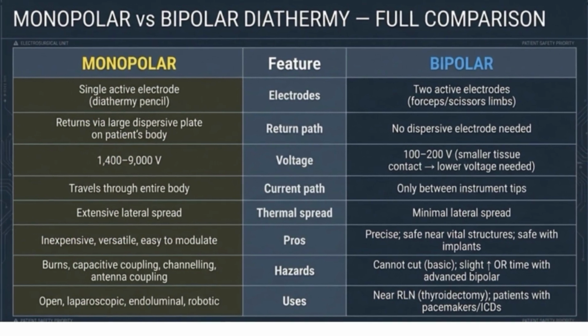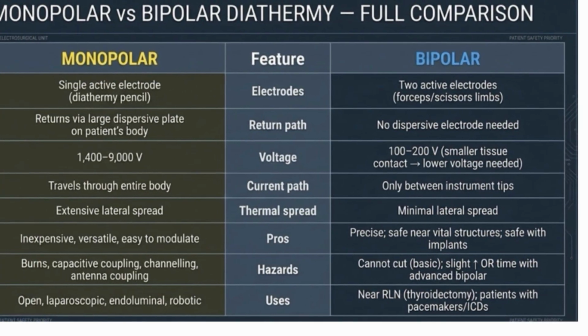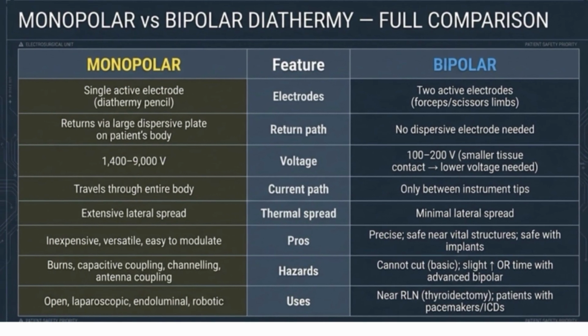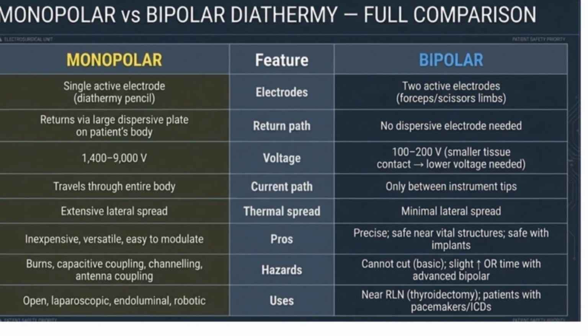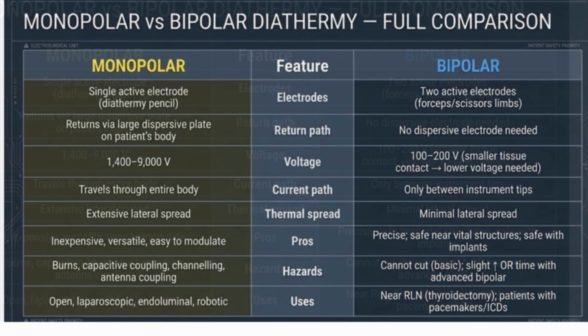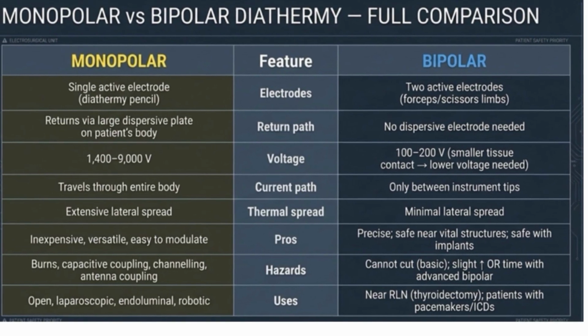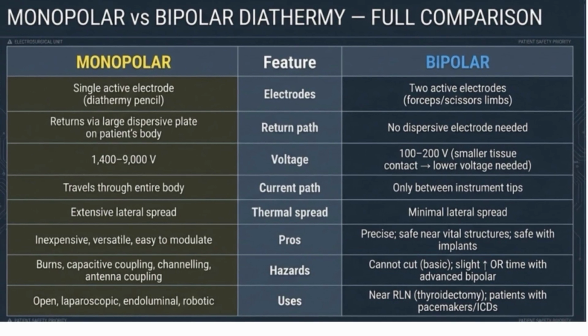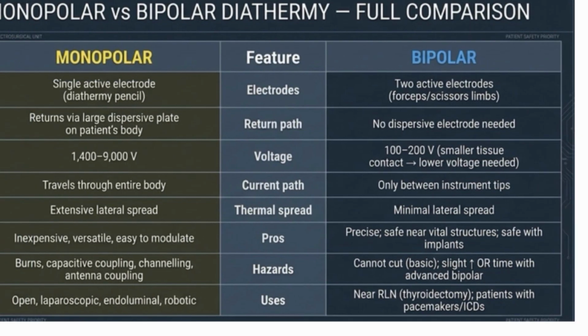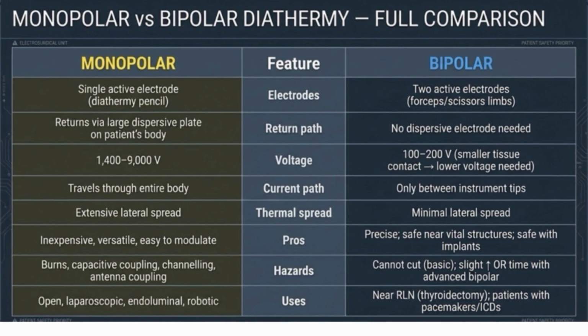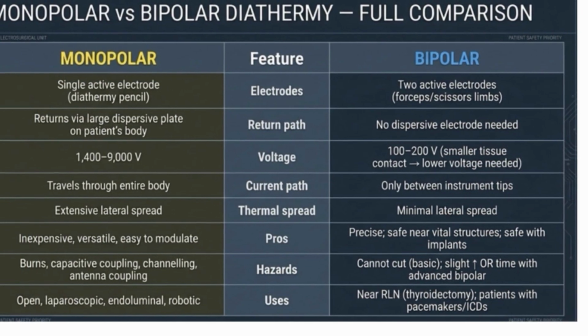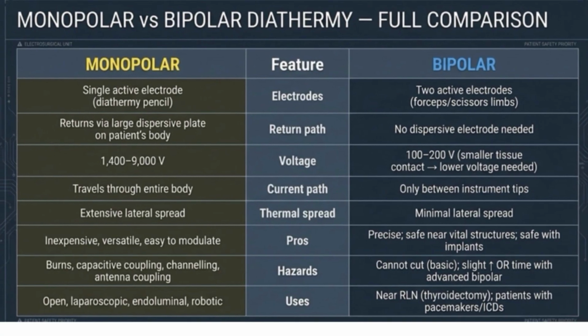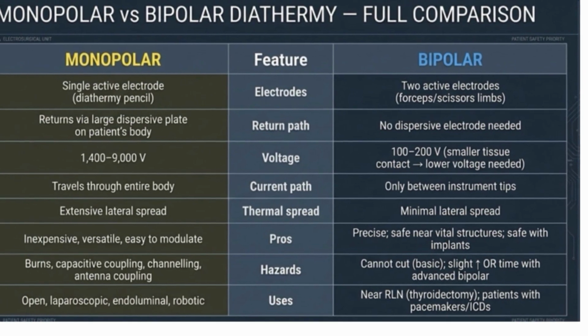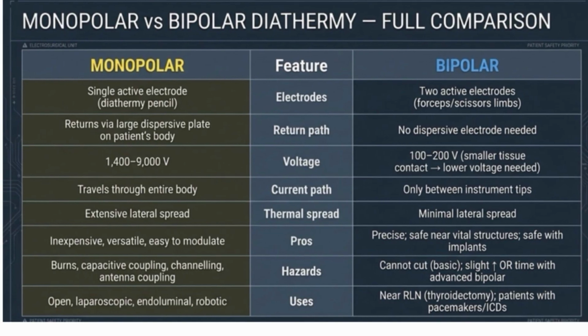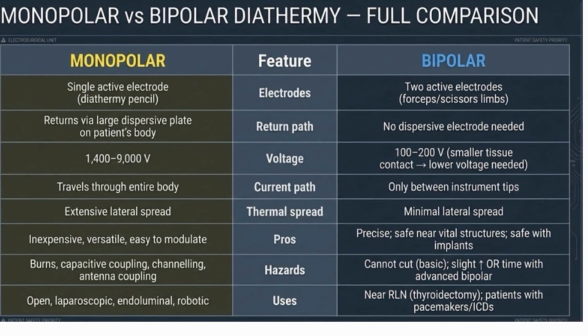The differences between monopolar and bipolar. Monopolar has a single electrode; the diathermy pencil is used. In bipolar, there are two active electrodes; forceps or scissor limbs are used. In monopolar, the return path is via a large dispersive plate on the patient's body. In bipolar, no dispersive electrode is needed. The voltage is 1400 to 9000 volts in monopolar, and 100 to 200 volts in bipolar, with smaller tissue contact and lower voltage needed. The current path in monopolar travels through the entire body. It passes only through the instrument tips in bipolar. Thermal spread: monopolar has extensive lateral spread and bipolar has minimal lateral spread.